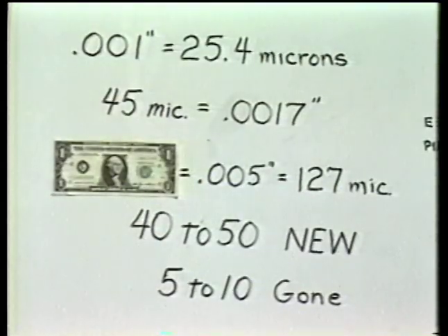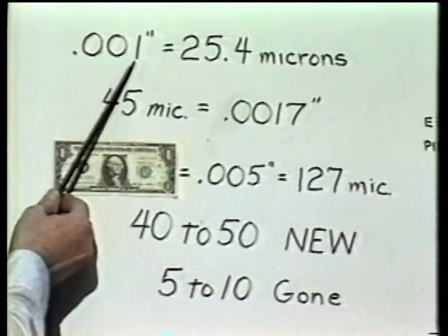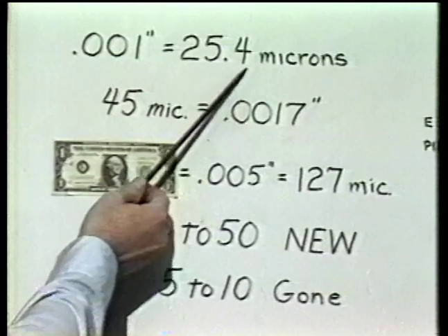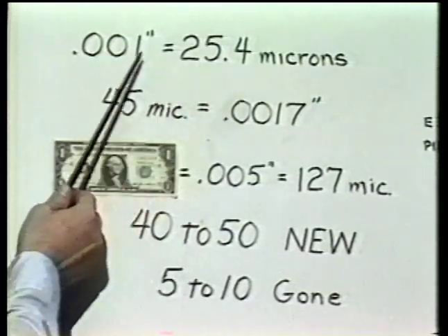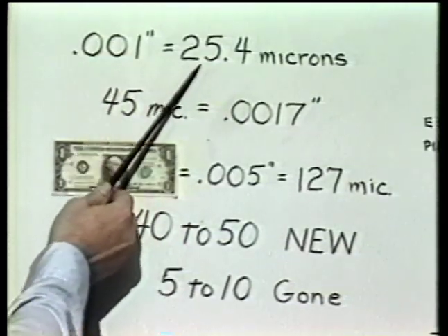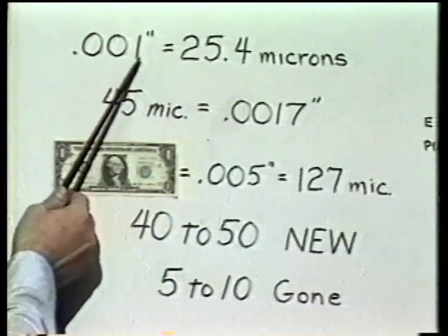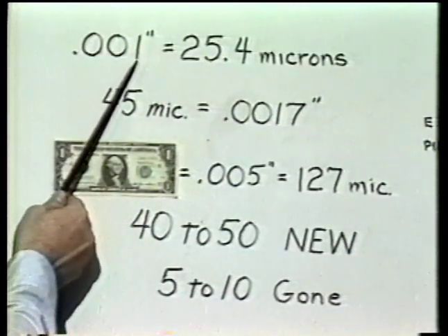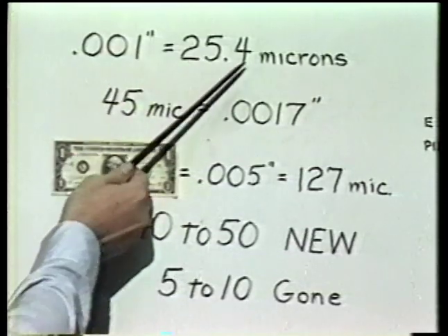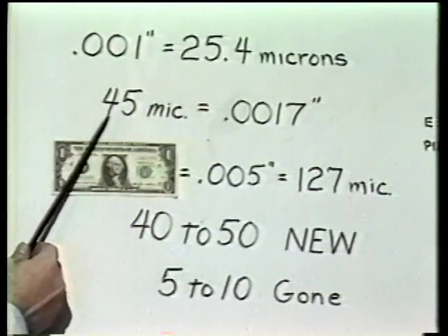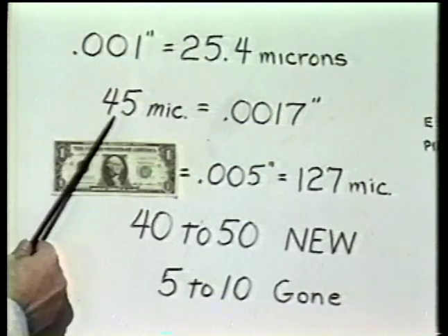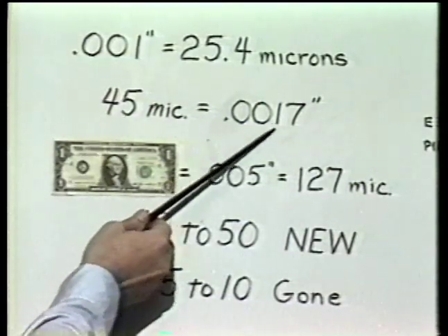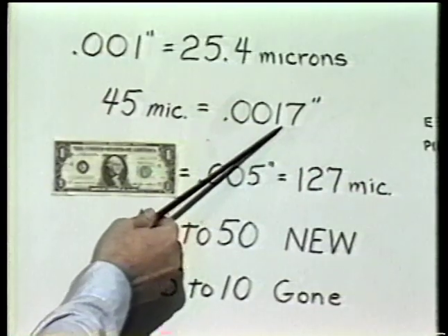Some technicians think that they can actually look at a video head tip to see how worn it is. I think it might be worth looking at some of the units that we're dealing with. 1/1000th of an inch represents 25.4 microns. So that means that each thousandth has 25.4 microns, or you'd have to divide 1,000th into 25 pieces for each of those microns. A new head protrusion reading would be about 45 microns, or about 1.7 thousandths, or a little less than 2/1000ths of an inch.